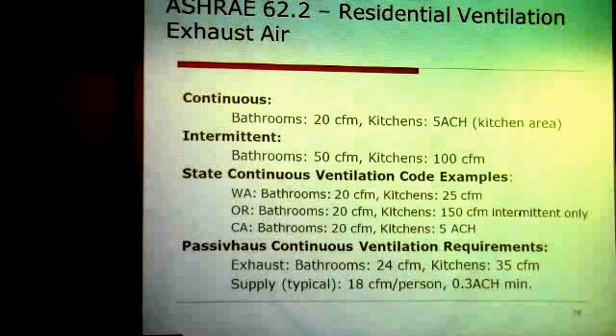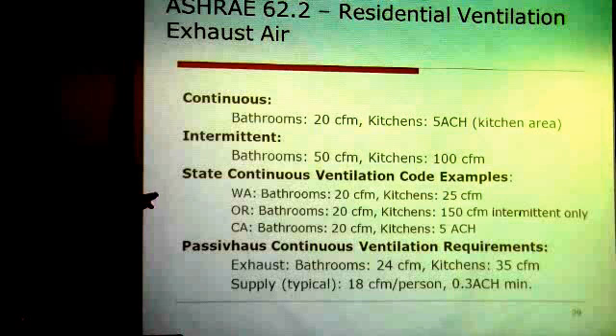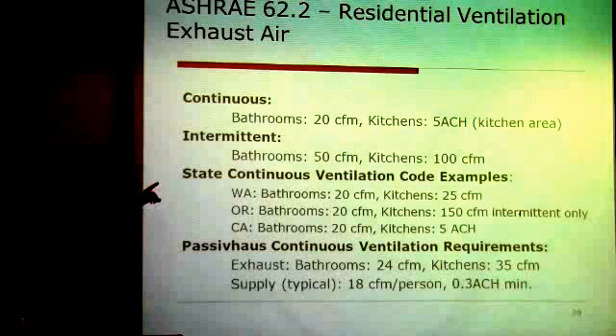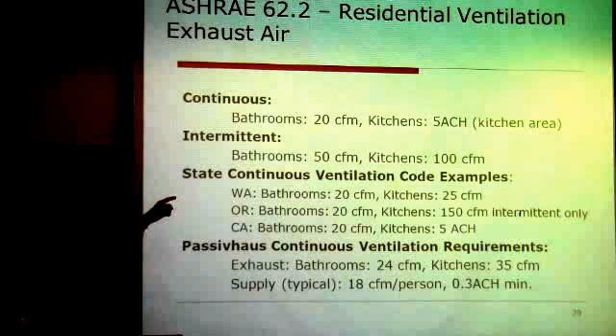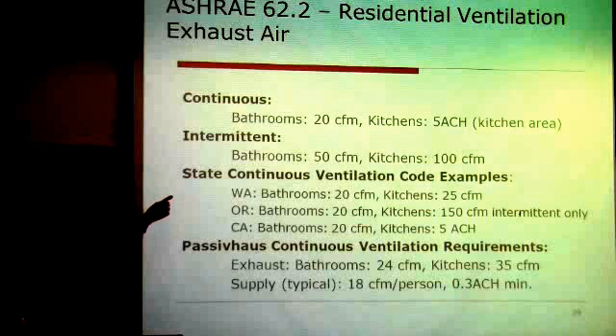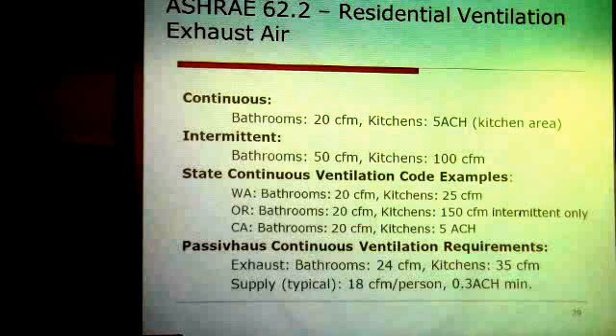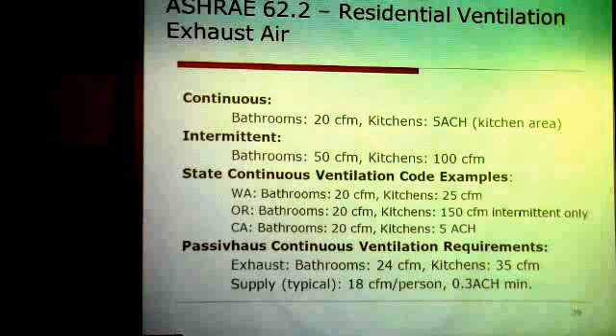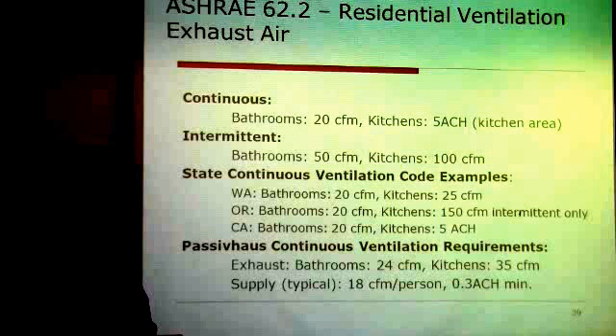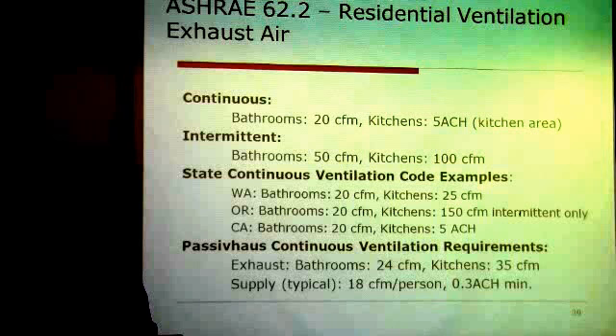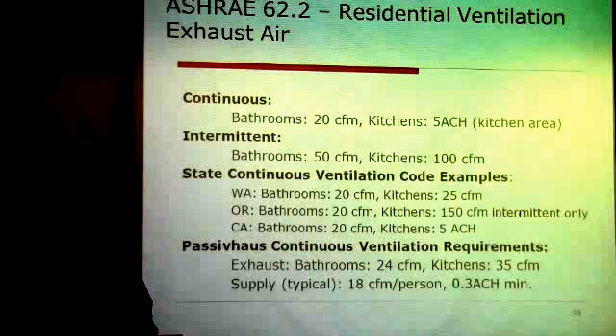So it says you can either do continuous or intermittent. And most common houses now do intermittent. Most stock homes, you have a bathroom fan that blows at least 50 CFM and kitchen fans that blow at least 100. Yeah. So I know we talked about CFM before of the heat recovery ventilators. Right. Do you know approximately what the ACH is with those on?